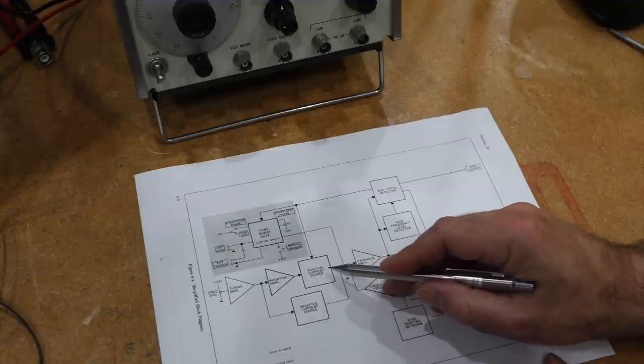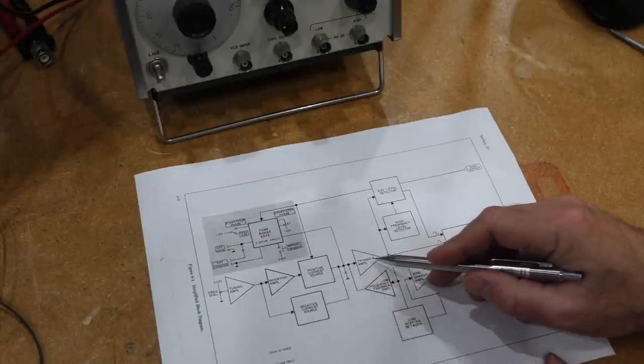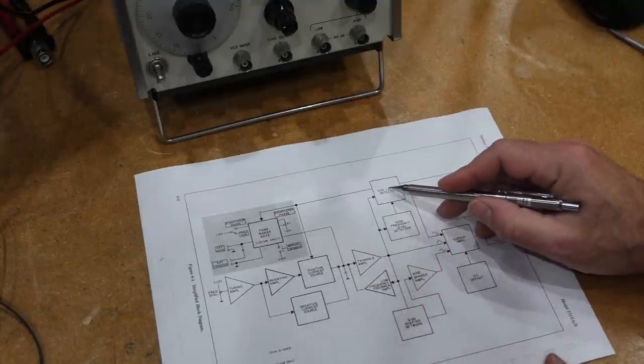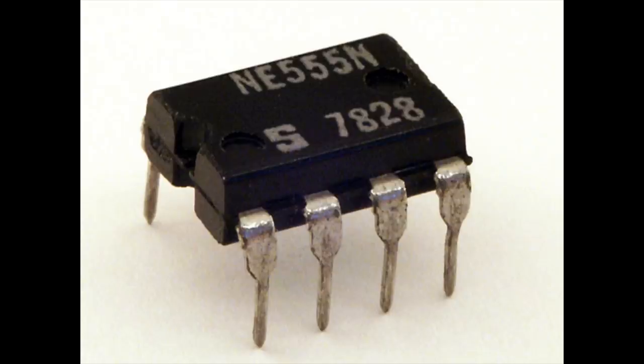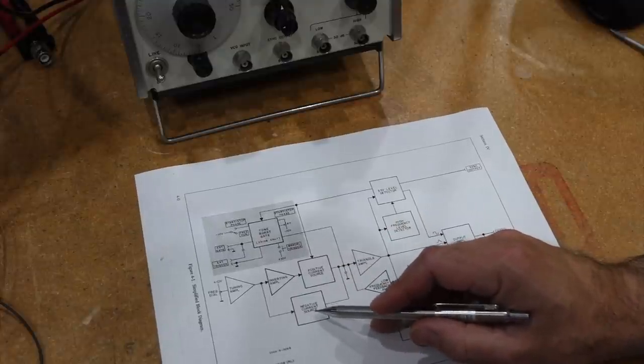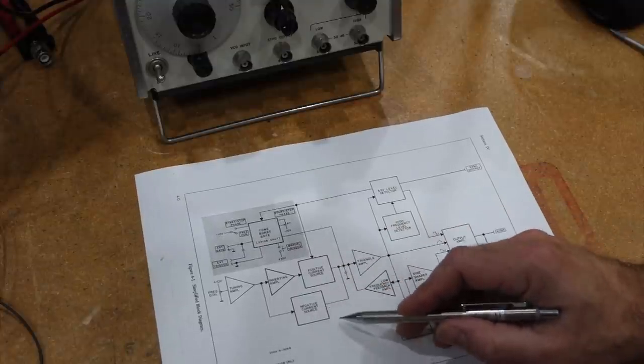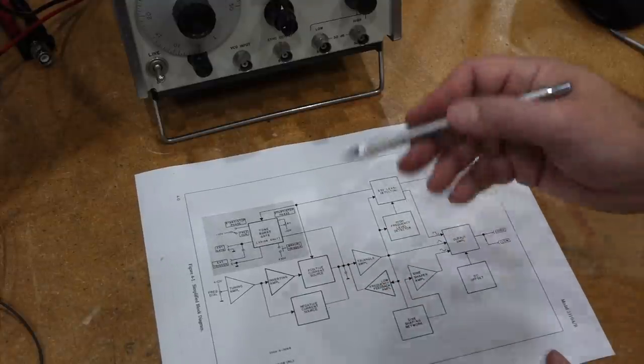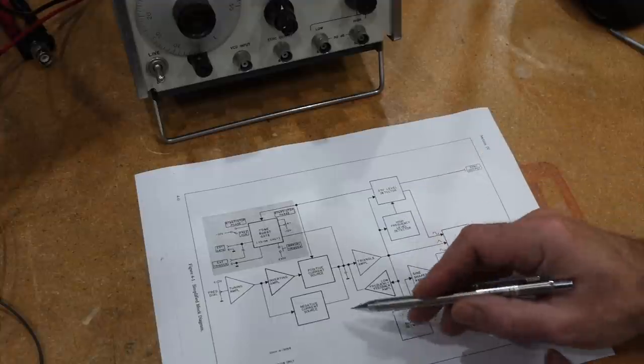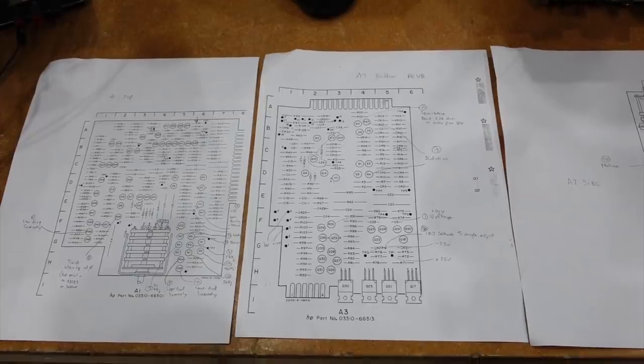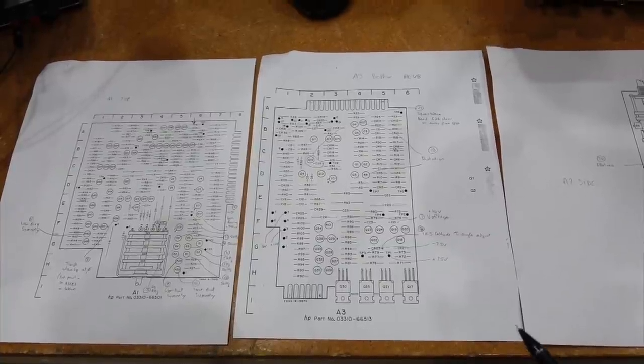By the way, this works similarly to the 3300A as explained in the previous video. It is basically a very refined version of a 555 timer producing a triangle wave, which is then shaped into a square wave and a sine. Fortunately, this calibration went swimmingly, so we don't really need to go into more details here. It also helps if you identify your adjustment points in advance.